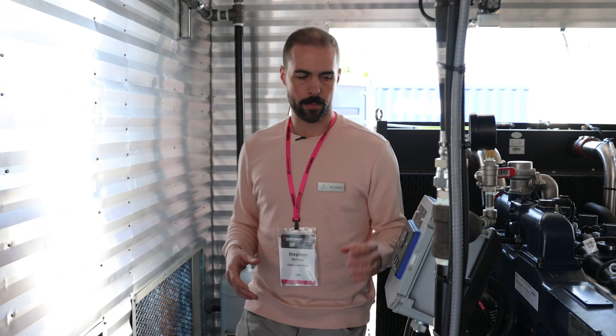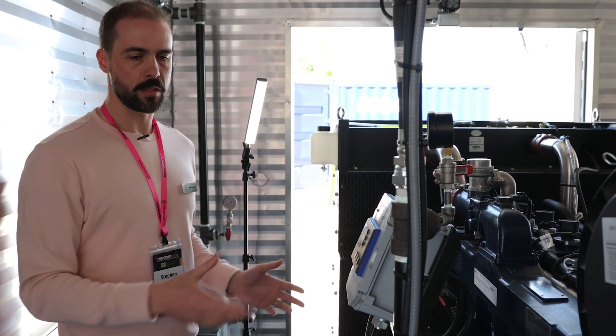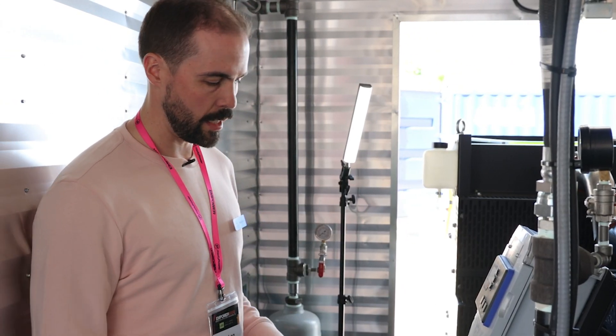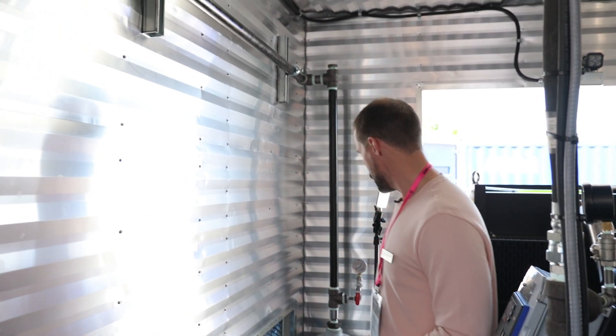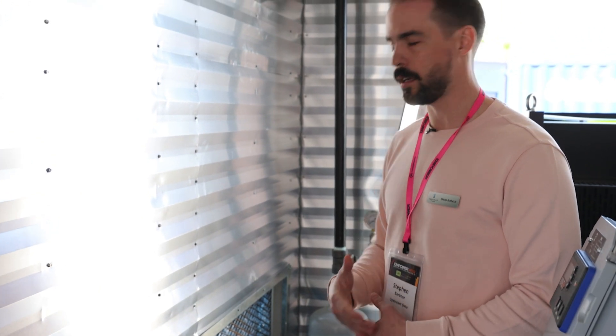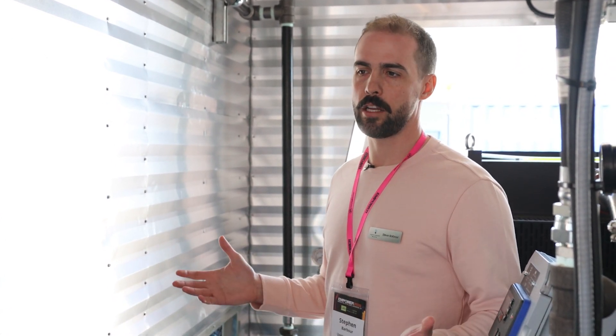This section is normally where operators come in and check the engine. If there are any alarms on the engine control panel, they can see that here. There are day tanks for oil. All the fuel gas is basically built into the system — we plumb the fuel gas into this scrubber here, which is really your end-of-the-line spot for any liquids that could come into your generator and knock that out. There are normal fuel gas pressure gauges to check when there are any troubleshooting events.